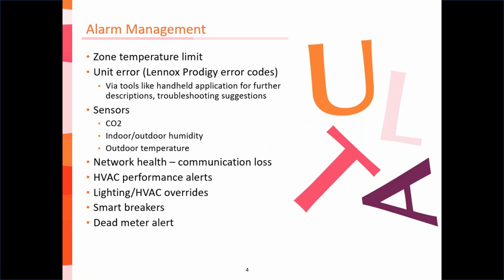Just a few examples of some of the alarms that we'll see. Zone temperature limits, so if the store is not maintaining the set points, and those are of course critical. We want to make sure we keep the store comfortable. We also get unit errors specific to the HVAC units. Where we have Lennox units, this is especially useful because we can get the Prodigy error codes directly from those units. And there are useful tools from Lennox, like their application, that can provide further descriptions of the issue and troubleshooting suggestions. We can provide more information to our HVAC techs when we're sending them out, and get a better idea of what the issue is with the unit without even being on site.